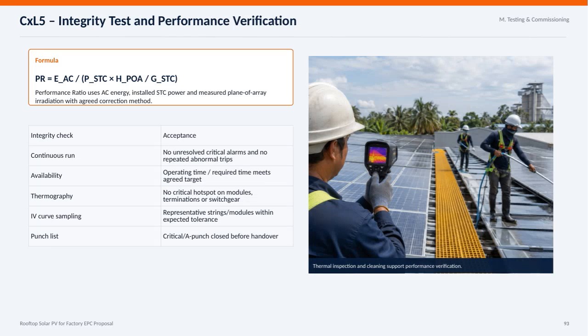Here, we're focusing on the integrity test and performance verification for the rooftop solar PV system proposed for the factory. The key formula for the performance ratio, or PR, is AC energy divided by the product of installed STC power and the plane of array irradiation adjusted by the standard conditions.